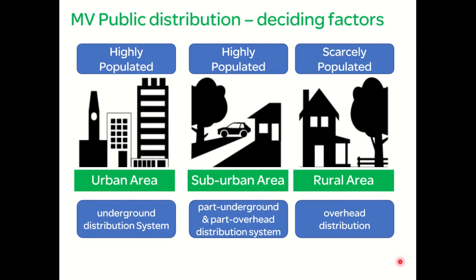Power is distributed using either overhead lines or underground cables. In urban areas, due to high-rise buildings in close vicinity, an overhead structure of distribution lines cannot be implemented — here power is distributed using underground cables. In suburban areas, the distributor has a choice to implement the scheme using either overhead lines or underground cables; overhead lines cost less than underground cables, and the choice can also result from environmental conditions, with areas of heavy rainfall usually having underground distribution. In rural areas, distribution through underground cables would be very expensive due to large geographical spread, therefore overhead lines are used.